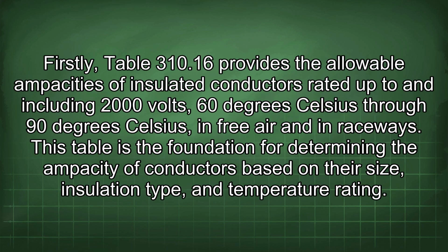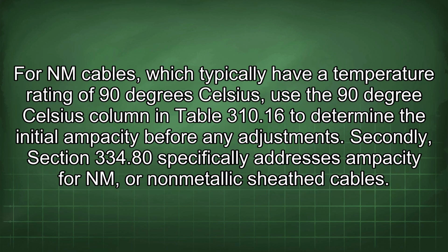Firstly, Table 310.16 provides the allowable ampacities of insulated conductors rated up to and including 2000 volts, 60 degrees Celsius through 90 degrees Celsius, in free air and in raceways. This table is the foundation for determining the ampacity of conductors based on their size, insulation type, and temperature rating. For NM cables, which typically have a temperature rating of 90 degrees Celsius, use the 90 degrees Celsius column in Table 310.16 to determine the initial ampacity before any adjustments.